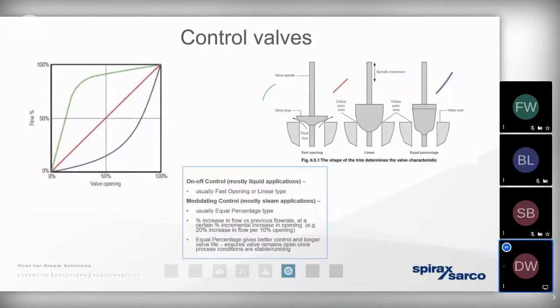And it's also important to give thought to the control valve characteristics themselves, namely the design of the plug, the valve seat. And that's because that's going to determine the speed of operation. So typically, we recommend an equal percentage characteristic, as this is going to give us a far better control of the steam. But it also means that the valve will spend less time sat close to its seat. Because from previous presentations, you'll appreciate that when a valve spends a lot of time operating close to its seat, that's when we're likely to get the abrasive and erosive nature of wet steam really affecting the passage of energy onto the process. And that's when we're going to get an inefficiency, maybe even a nuisance trip out of any high limit valve.